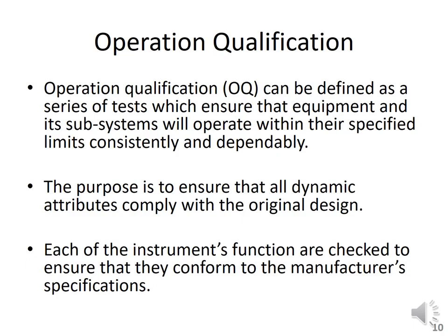Okay, so depending upon your needs and the complexity of the system, operational qualification can be combined with the installation qualification, or even the performance qualification, which is the next one, right? So operational qualification can be paired up with the previous qualification and with the upcoming qualification, just for making things smoother and making the system work nicely.